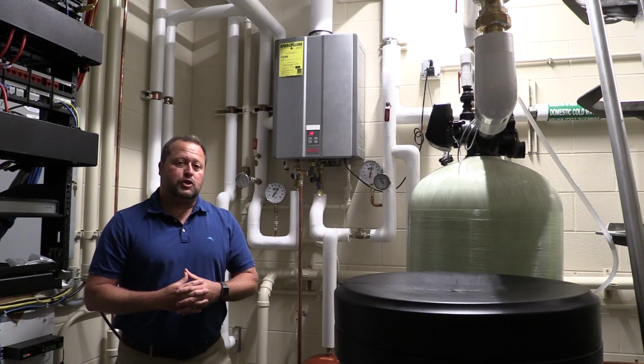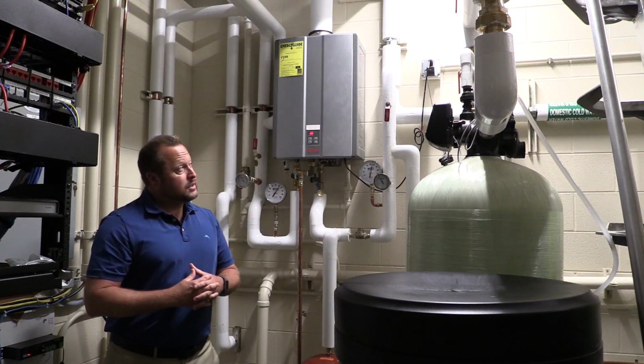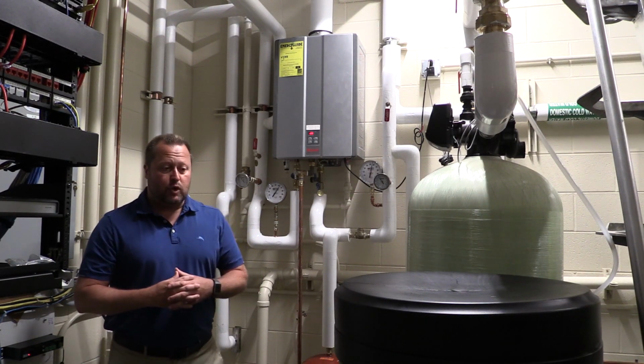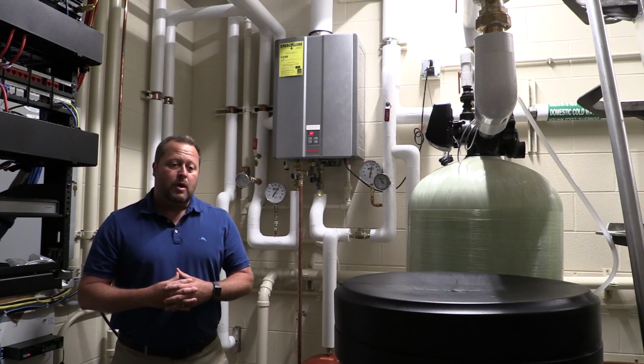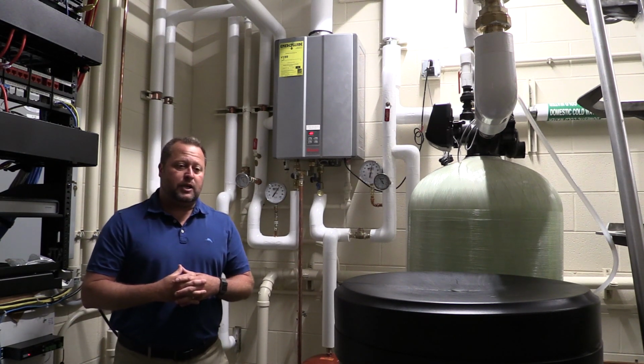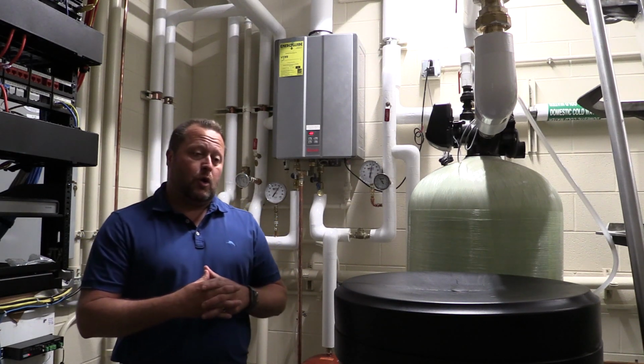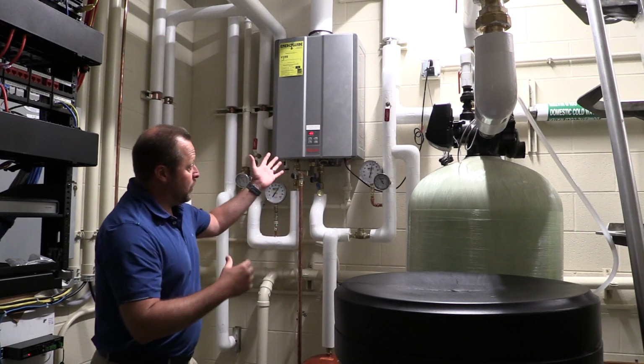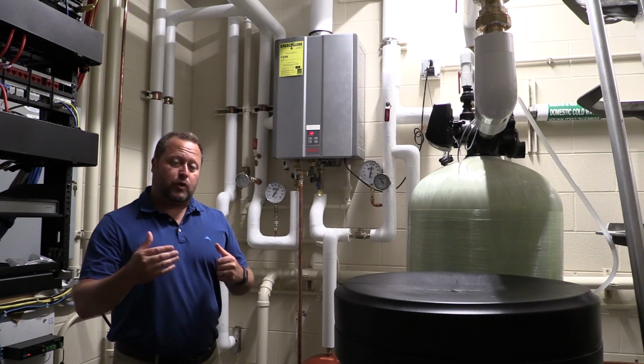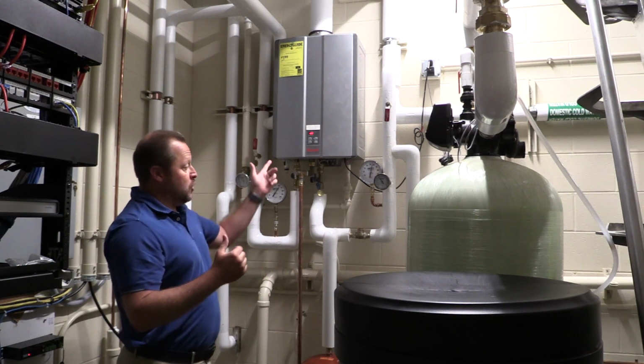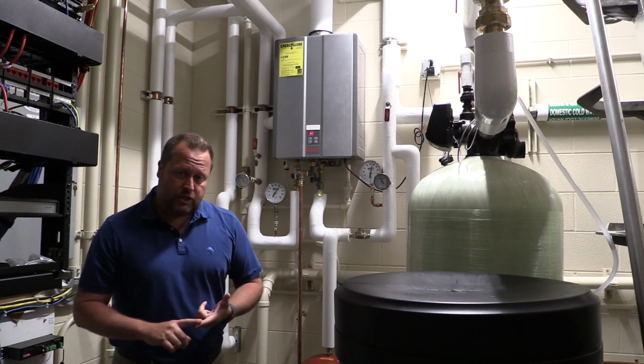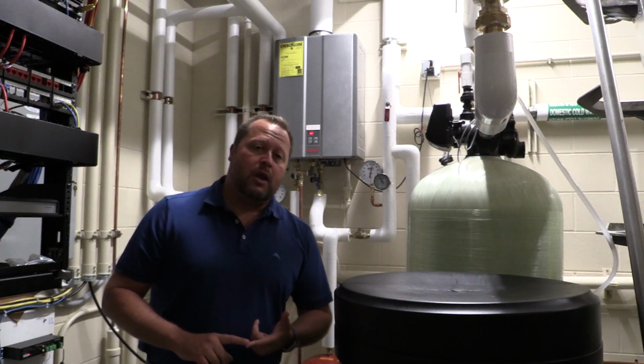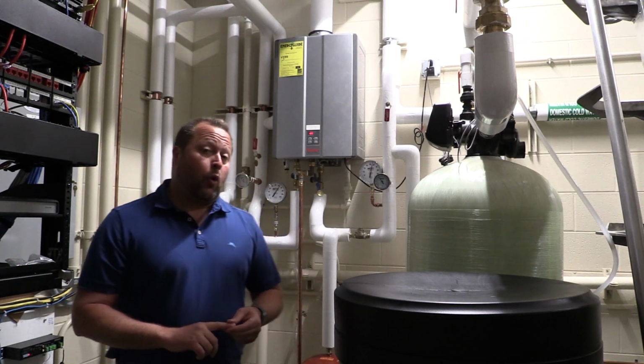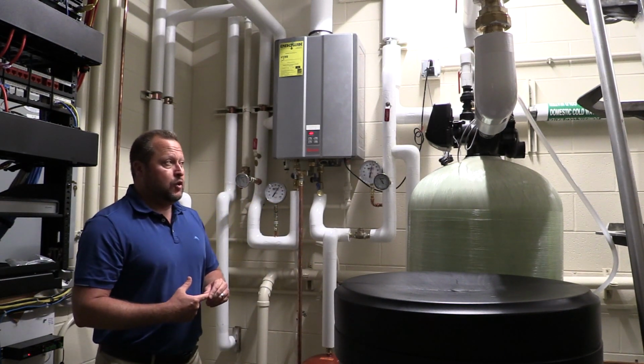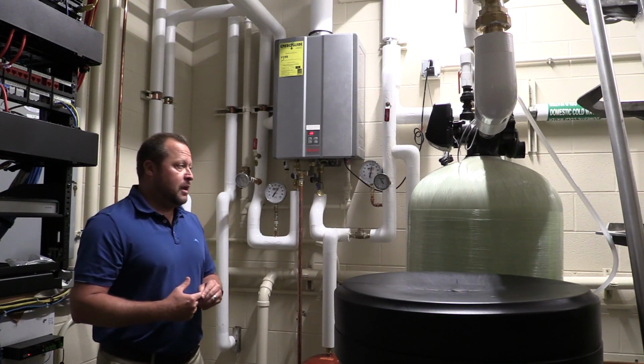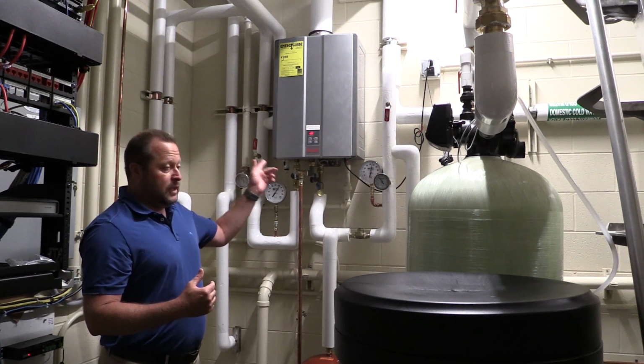Okay, so I want to also touch on the warranty of the product. It is a residential unit. The residential and commercial are in essence the same unit, but when you put a residential in a commercial application, it assumes a commercial warranty. So in essence, again, the components are all the same. It's just you get a black jacket with commercial, and residential you get a silver jacket. So the warranty is an 8-year heat exchanger, it's 5-year on parts, and it's 1 year on labor. So in order to maintain the warranty, you do need to service this annually. And basically the annual service is cleaning out the heat exchanger.